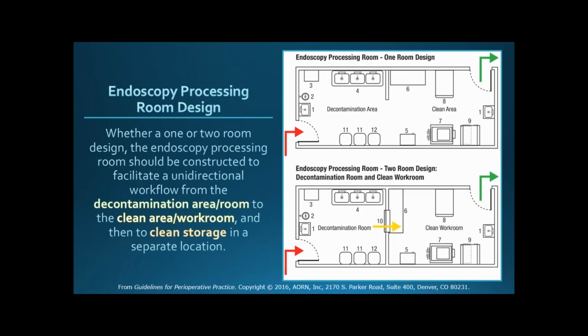Especially when you're talking about endoscopy room design, if you're getting to the point where you're going to be designing and creating a new workspace, there are two different ways that AORN recommends you have that workflow. It always needs to at least be unidirectional. If you have a one-room design, you need to make sure that dirty is always on one side, clean on the other side, and that everybody follows that pathway, so you don't have contamination to the clean side from the decontaminated side. You try to separate those two as much as possible. If you are able to have two separate rooms, having your decontaminated side at negative pressure is something that they will check on, and trying to have your clean workroom at positive pressure.